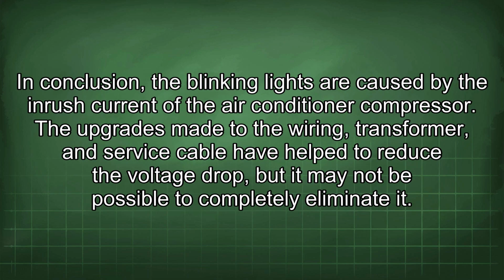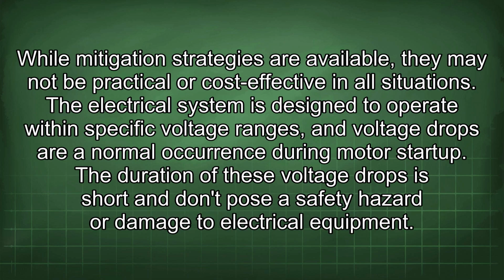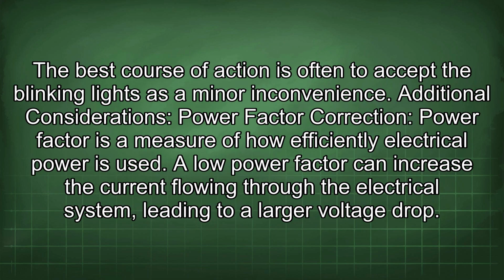In conclusion, the blinking lights are caused by the inrush current of the air conditioner compressor. The upgrades made to the wiring, transformer, and service cable have helped to reduce the voltage drop, but it may not be possible to completely eliminate it. While mitigation strategies are available, they may not be practical or cost-effective in all situations. The electrical system is designed to operate within specific voltage ranges, and voltage drops are a normal occurrence during motor startup. The duration of these voltage drops is short and doesn't pose a safety hazard or damage to electrical equipment. The best course of action is often to accept the blinking lights as a minor inconvenience.